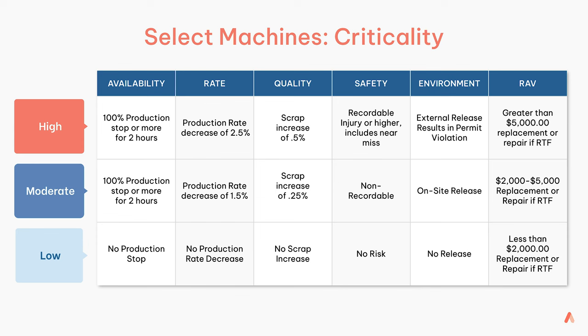We talk about machine criticality. This is an example of an OEE-based criticality matrix for manufacturing. You can see six parameters being quantified at the level of high, moderate, and low. You want to be able to quantify each of these boxes under each column heading and share that with your stakeholders so that you can develop consensus — but they have to be measurable, not just random opinion. You need to construct these criticality matrices against the assets or machines in your facility and the business plan for production, because at the end of the day, we all get paid from product put out the door and sold.